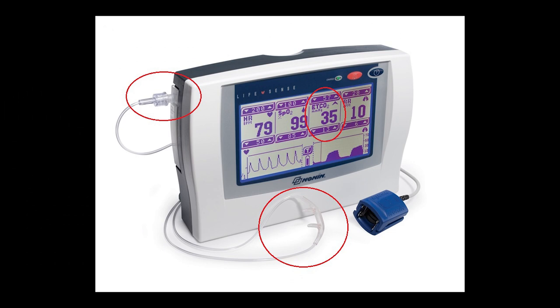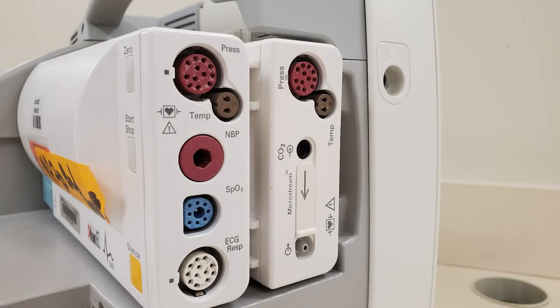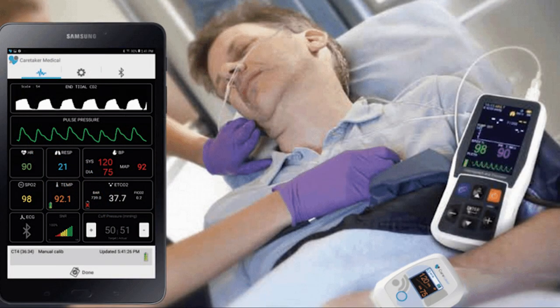Sidestream sensors are located at the monitor itself and use a small hose to take a sample of the gas exhaled by the patient. There's a small delay in the data as the gas travels through the line, but the sensor is protected from damage because it's located in the monitor itself. These EtCO2 monitors are found in step-down care units, post-anesthesia care units (PACUs), and general patient rooms. All types of EtCO2 monitors show quick changes in a patient's physiology, so end-tidal monitoring is becoming a patient care standard.